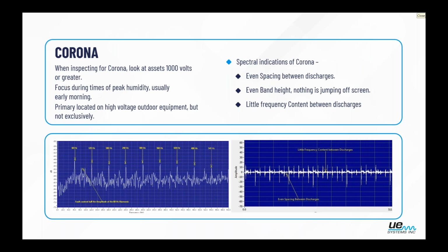So out of the events that we're looking for, the first one I'd like to go over is corona. As a note, when we are looking for corona, that does occur on assets 1,000 volts or greater, so those are what I'll be starting off our inspection with. Typically, the higher the humidity, the greater your occurrence of corona. So times of greater humidity, early morning, would probably be the better time to inspect for it. Typically, where we see it the most is on high voltage outdoor equipment, but that is not exclusive.